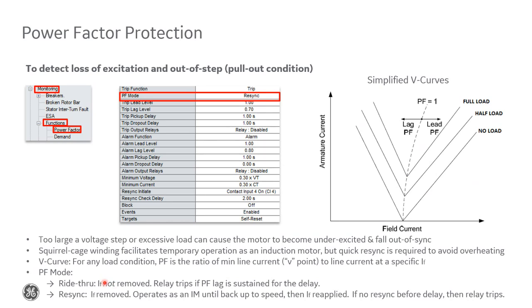If we set this mode to ride through, the relay will not immediately remove the DC supply. We'll attempt to wait and see if this was just a temporary dip. If the motor didn't completely pull out, it's usually able to recover itself using the squirrel cage in induction mode to come back up to speed. But if the power factor doesn't recover after the set time delay, then the motor has likely fallen too far out of sync and will trip offline.